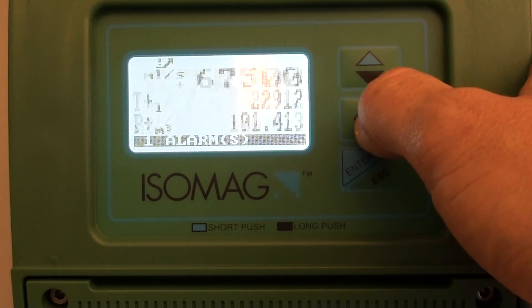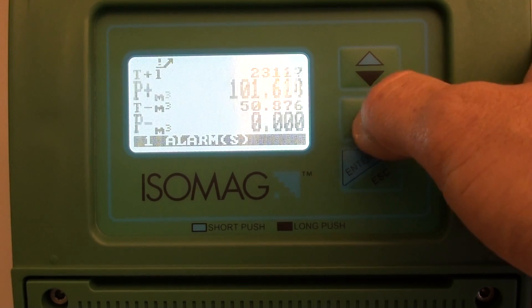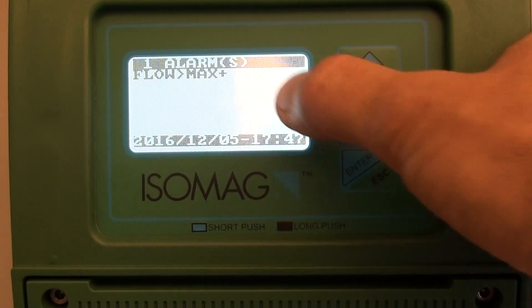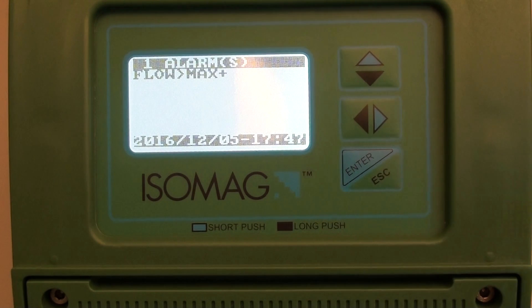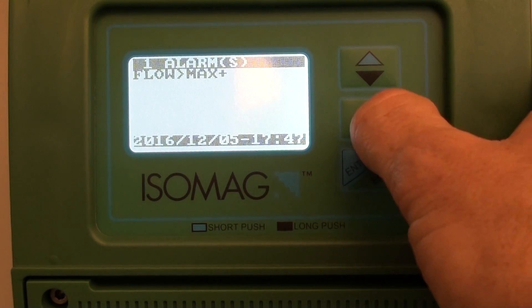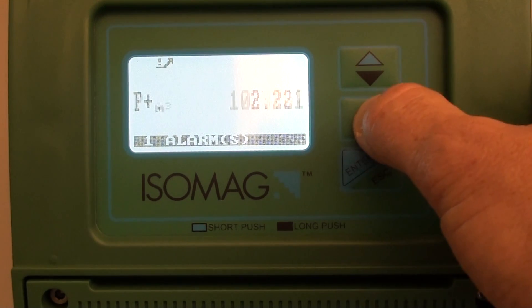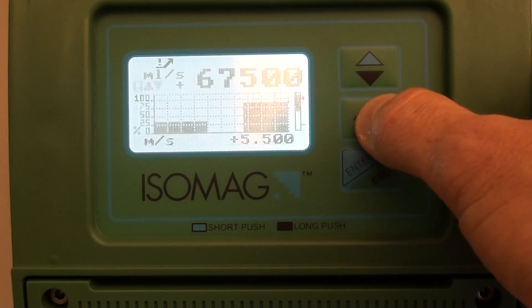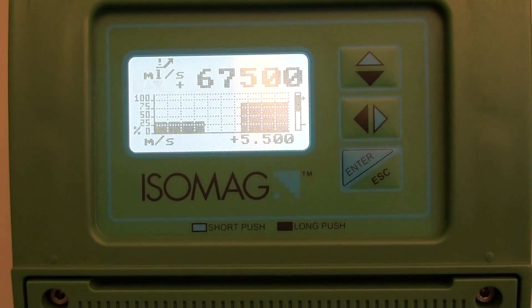You can see that I have one alarm — flow rate above max — because it's set to 70%, and I've selected a flow rate to be simulated equivalent to 90% of the full scale.